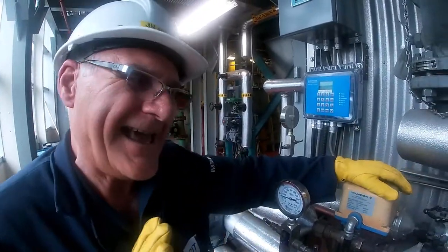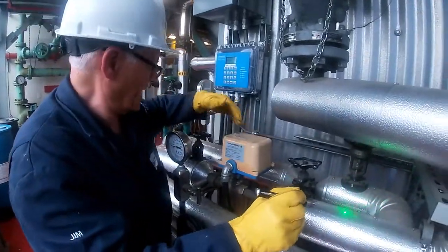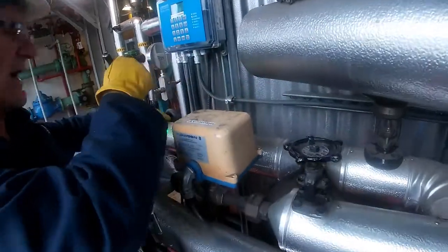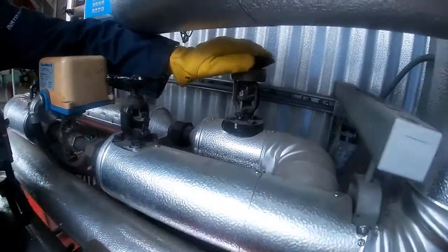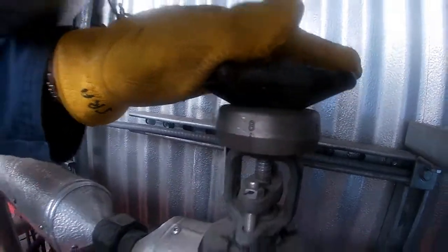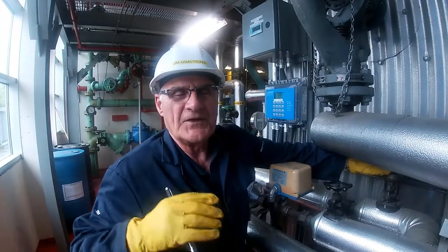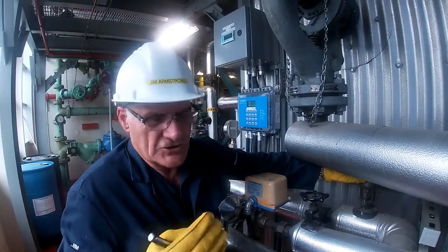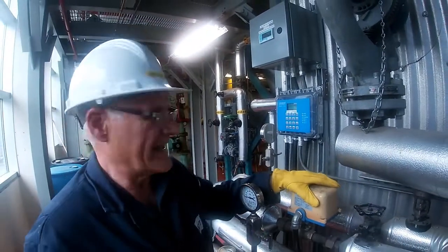If the conductivity can't come down, i.e. it's really high in there, behind it, right here, is a bypass valve. This bypass valve has calibration marks on it, and we can actually open or close that valve. So if the conductivity is too high and you can't get it down inside the 30 minutes, you open this valve up a little tiny bit, and the operator will do that. It's a matter of opening it up so you finally get to the point where this guy is controlling. It's almost like a gap action control system, where this is the major and this is the minor. And basically that's how it operates.